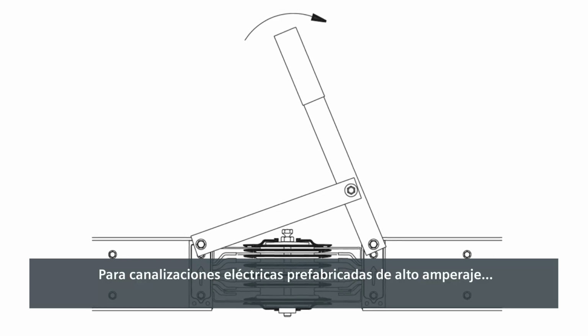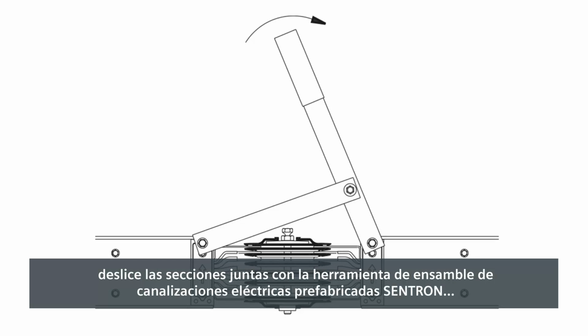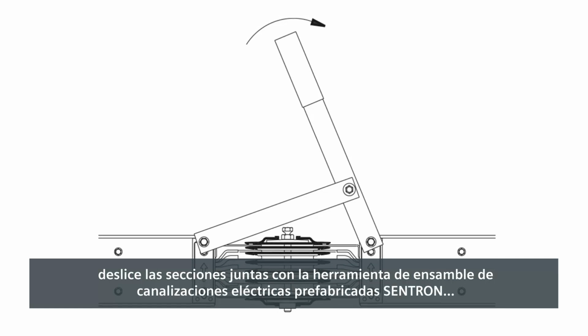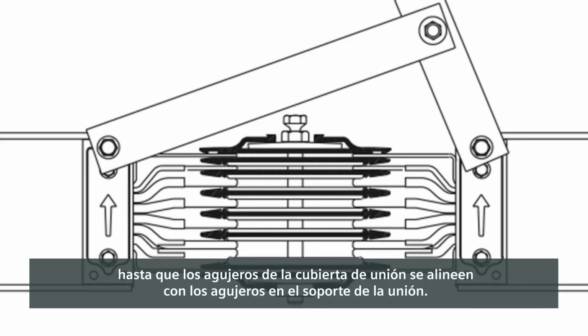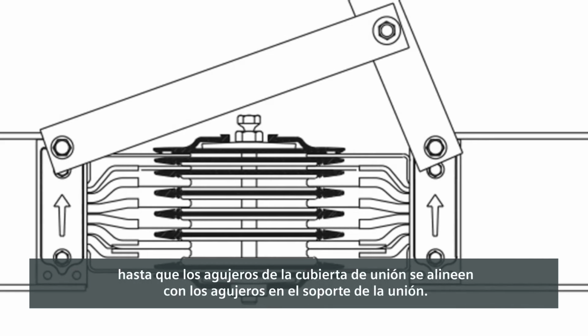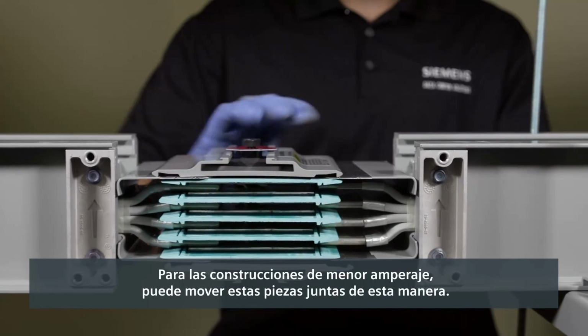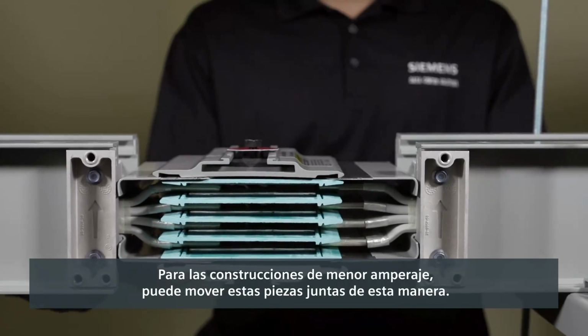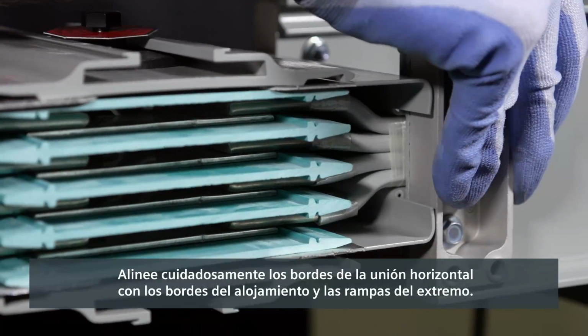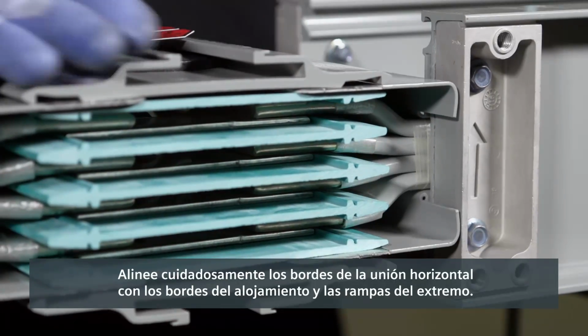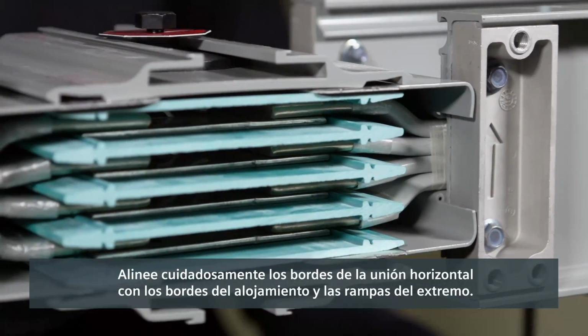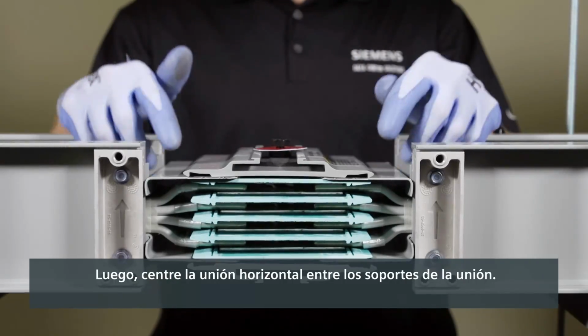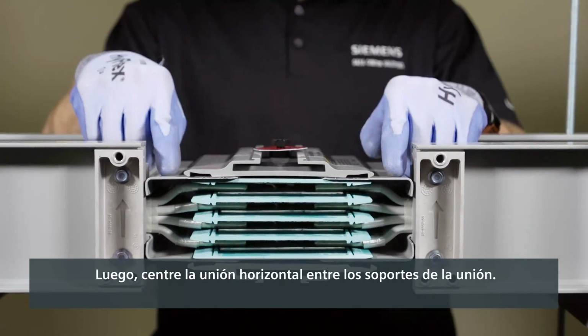For high amperage busway, slide the sections together with the Sentron busway assembly tool until the holes in the joint cover align with the holes in the joint support. For lighter amperage constructions, you can move these pieces together like this. Carefully align the edges of the joint stack with the edges of the housing and end ramps. Then, center the joint stack between the joint supports.